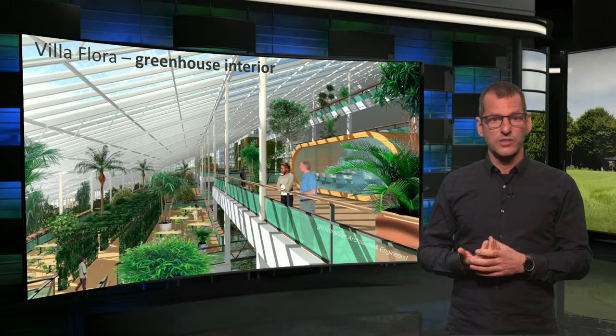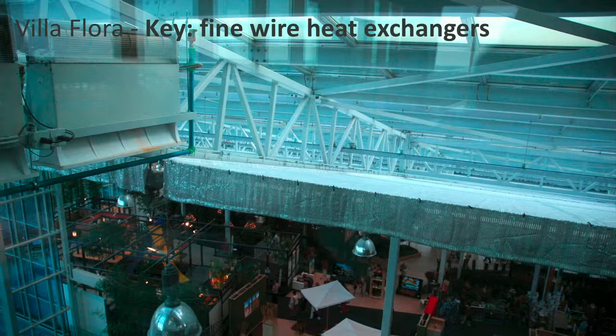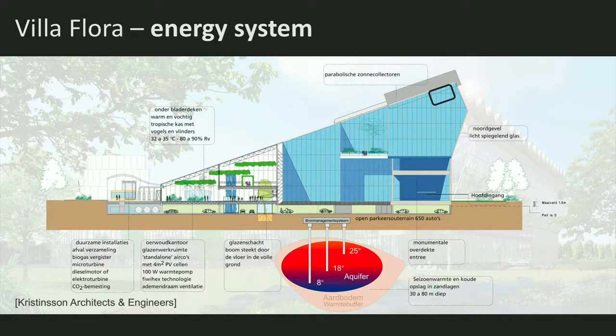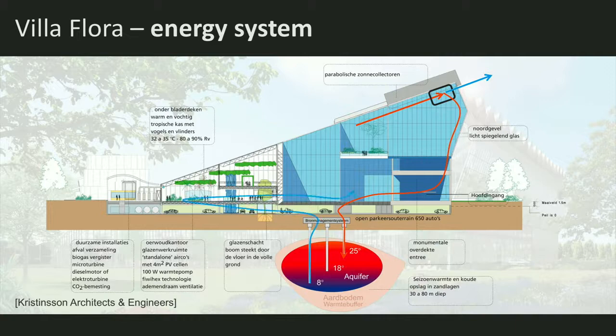This is an artist's impression of the impressive greenhouse space. Now watch carefully — this is the same greenhouse seen from above. On the left top, you see a strange apparatus. This is a highly efficient heat exchanger that transfers the hot air of the greenhouse, above the awning in the middle, to water. What happens next can be seen in the cross-section of Villa Flora: hot air that has risen against the glass roof goes to the heat exchanger and transfers its heat to water, taken to the seasonal storage in the underground. In summertime, cool water from the well is used to cool down the building, but due to irradiation and internal heat sources, air will warm up anyway and rise to the roof — and here the story starts all over again.